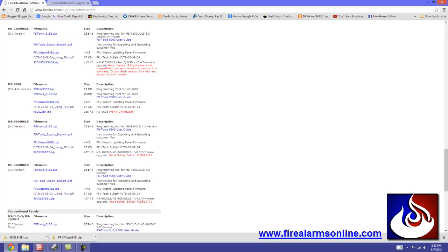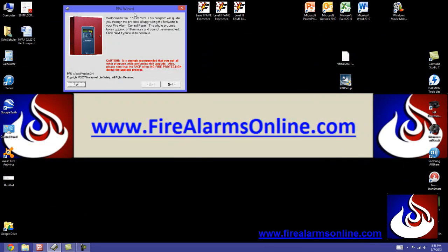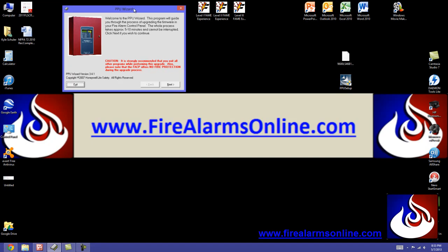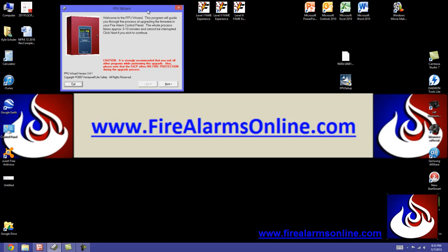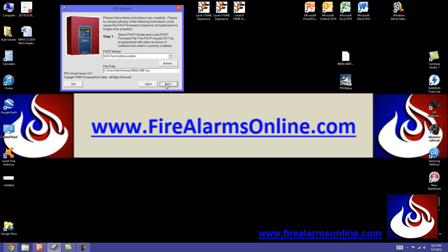So now, once you've successfully installed the PPU Wizard on your computer, you're going to open it up and it's going to look like this. It's got a little disclaimer here and everything. It's telling you it takes about 5 to 10 minutes to perform the whole firmware update. And the next screen, it's going to tell you to disconnect power, AC and DC to your panel. So I usually do that before I get started. So just disconnect all the power to the panel. And once you have this open, click next.